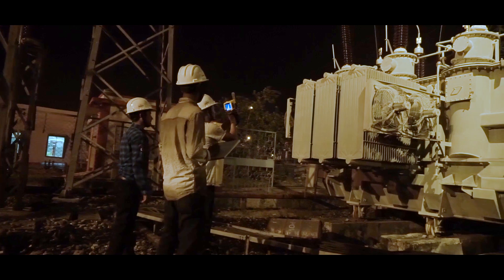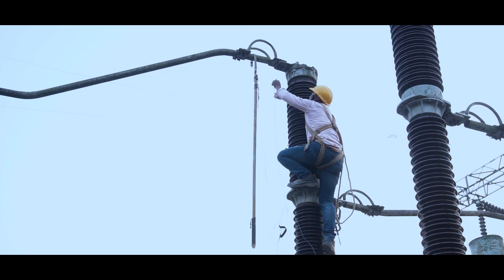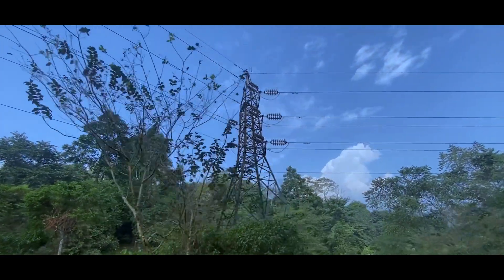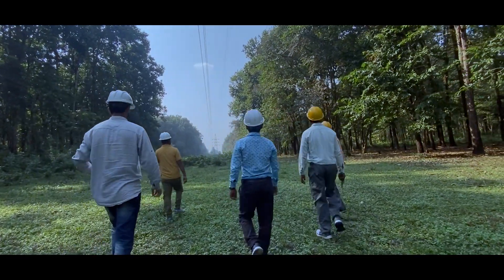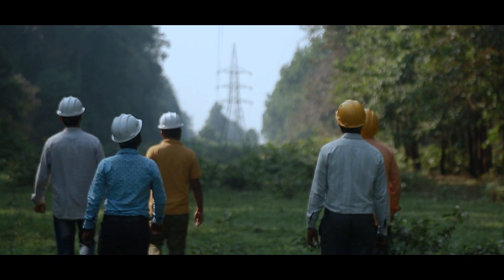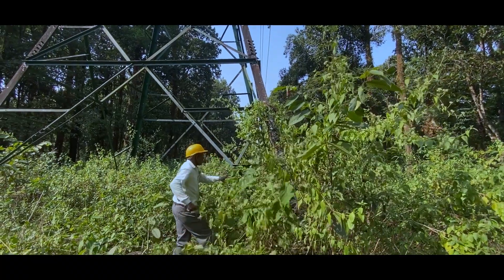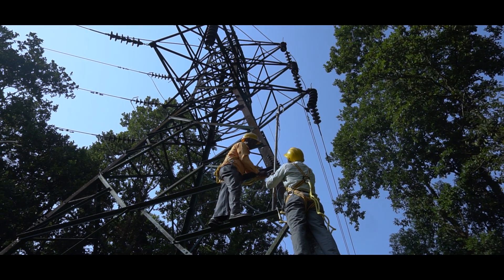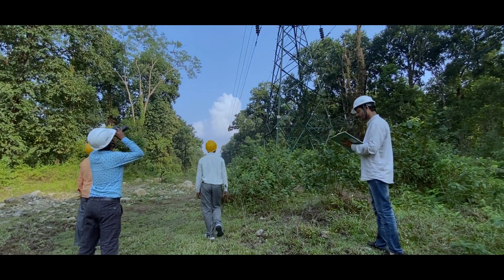One of the major challenges in the region is the difficult terrain of the transmission lines, especially at 66kV level. These lines go to dangerous wildlife areas, hence extra precautions like carrying firecrackers and protocols like giving prior information to the forest officials are followed. To ensure high availability and reliability, periodic line patrolling, route clearance, jumper checking and tightening, insulator checking and replacement, earth wire replacement, foundation checking and repairing, etc. are done for all lines at regular intervals.